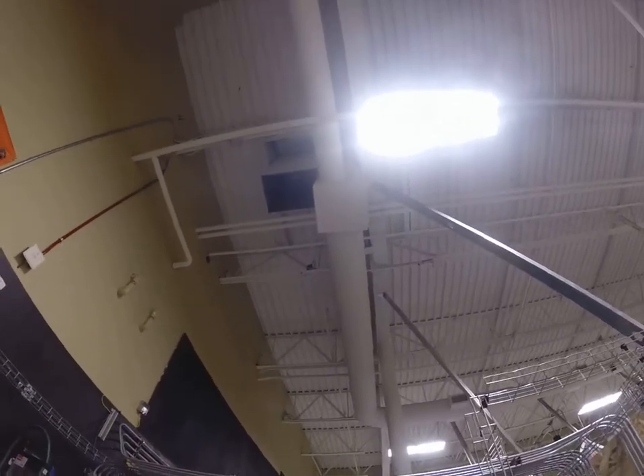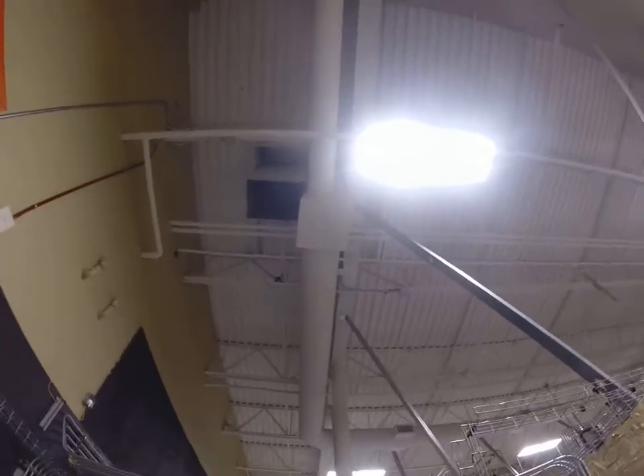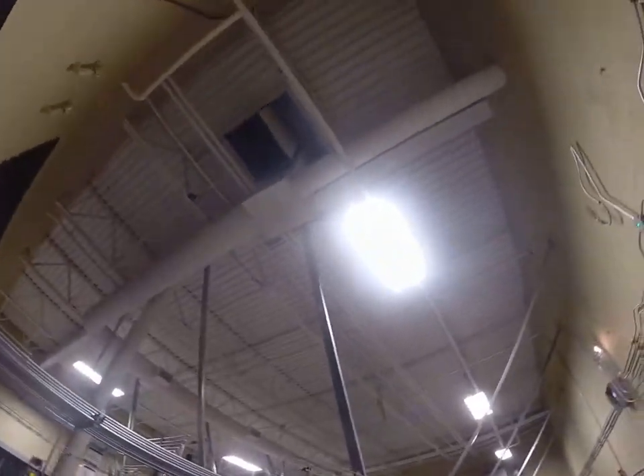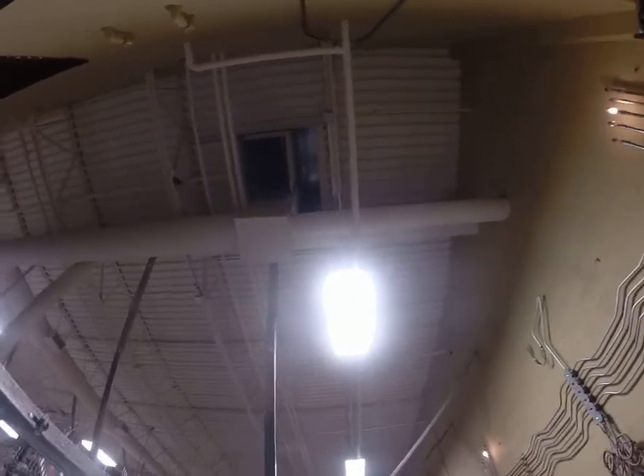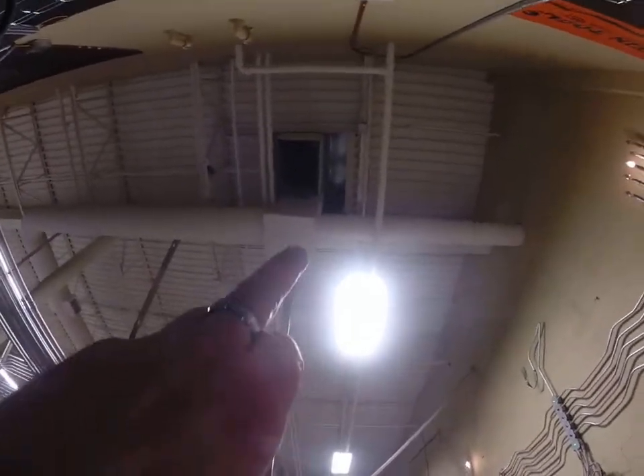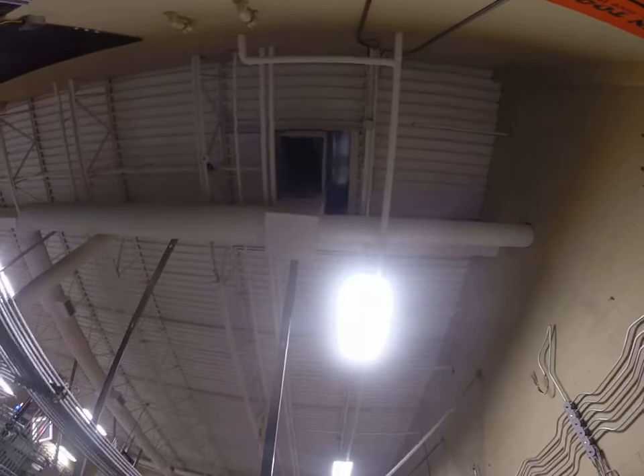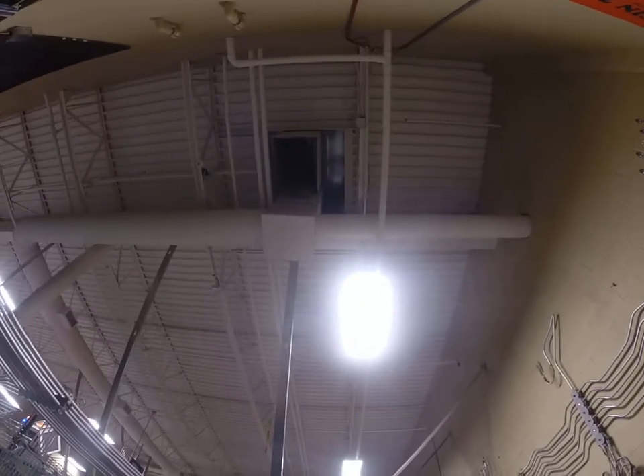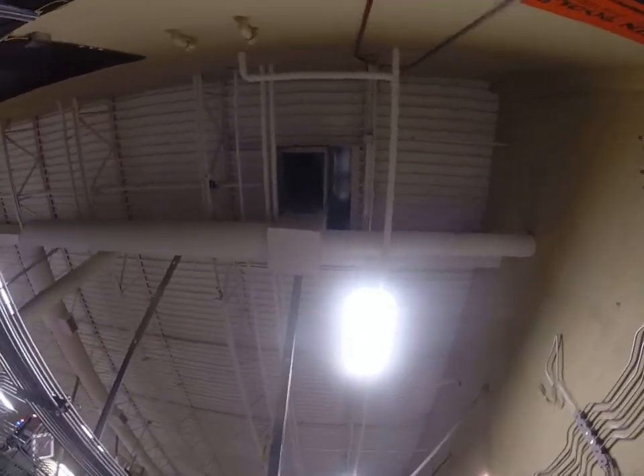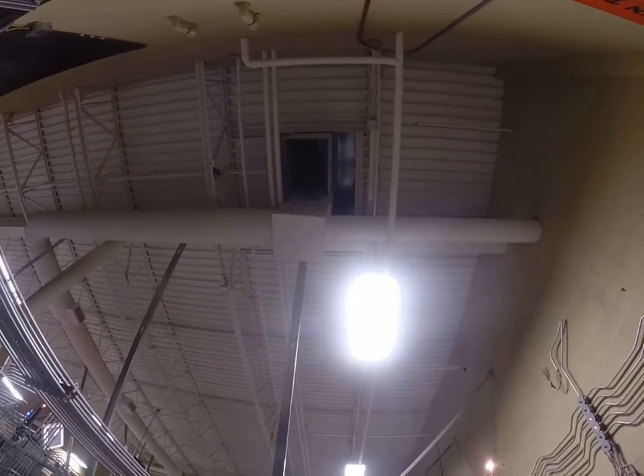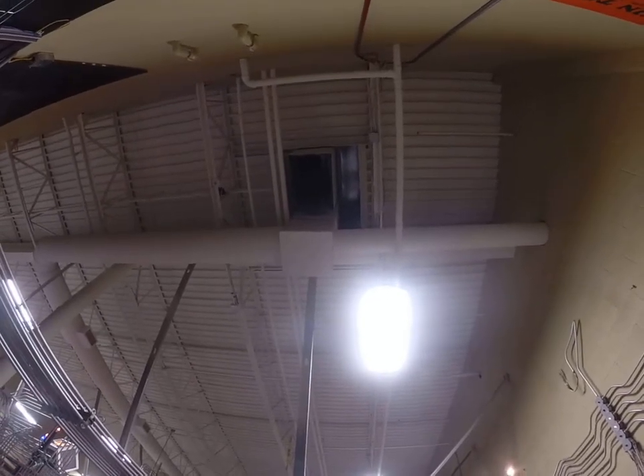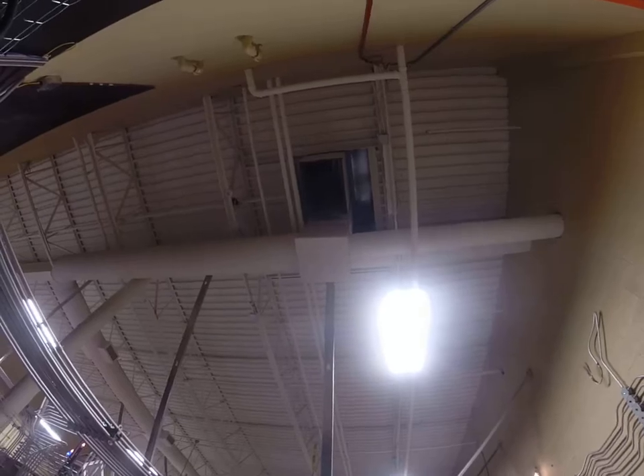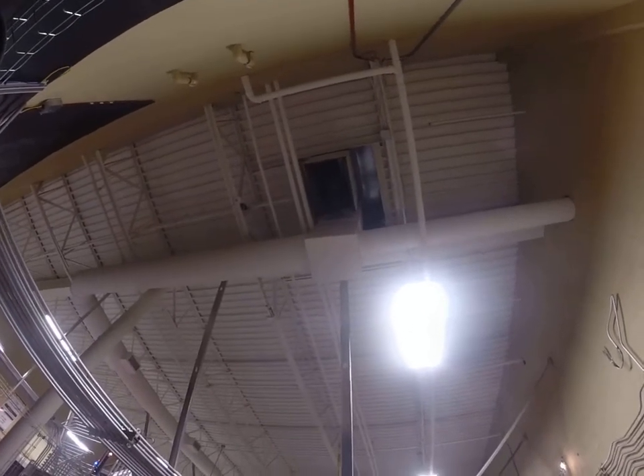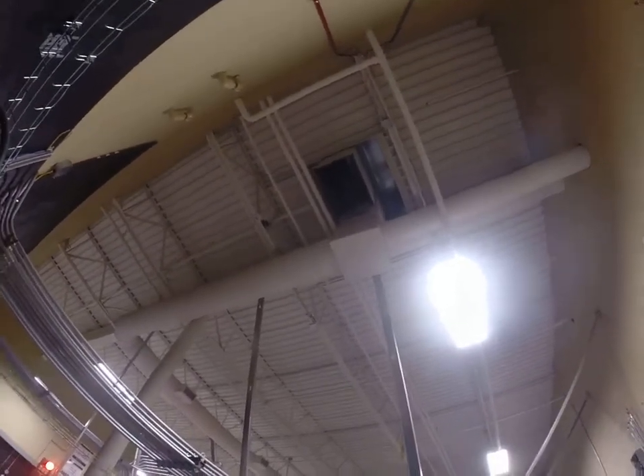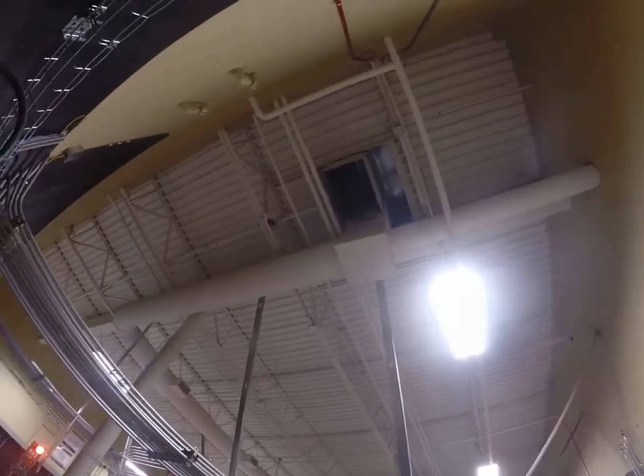So that 3-phase 208 or 480, whatever it might be, that feeds that unit goes up, and you can see there's a piece of seal tight in there with some fire alarm, white wire and red wire that goes into that seal tight. So you get your thermostat wiring and you've got your fan shutdown wiring going up into those units. So that's fire alarm. Of course, we'll talk more about fan shutdown, but for now, 2 conduits going up into every unit.